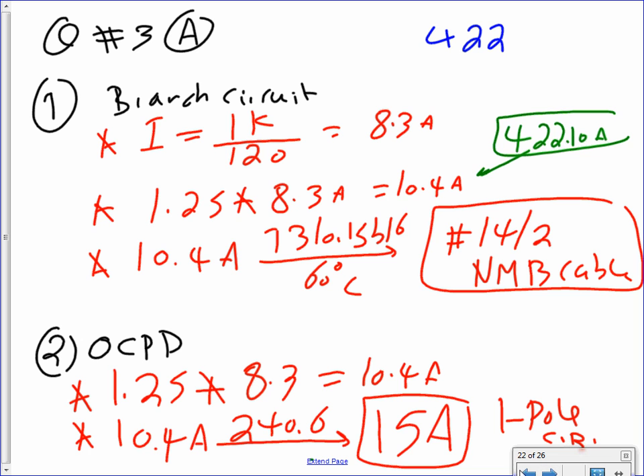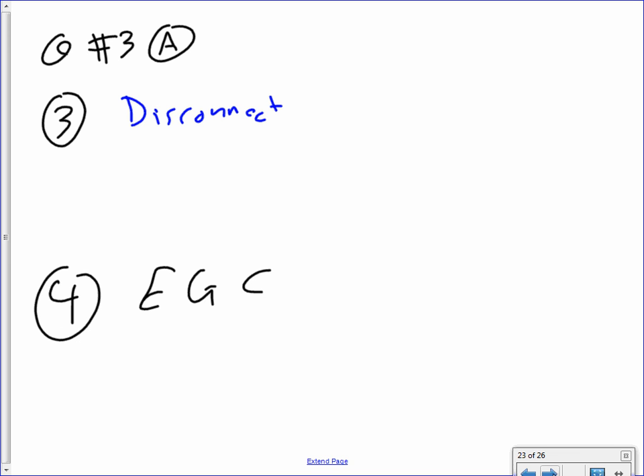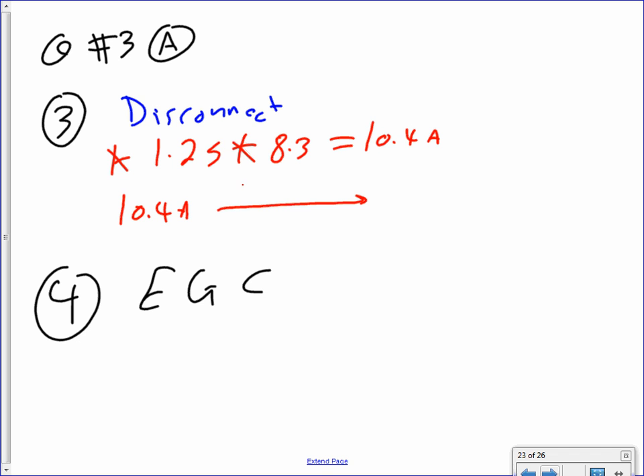Cool. Next, we need to go find the disconnect. What I do personally for the disconnect, my friends, is the same thing. I take the 1.25 continuous load multiplied by my 8.3 amps. The motor gives me 10.4 amps, and then you take the 10.4 amps. This is from 422.30, 422.31, I believe. That will get you guys a 15 amp snap switch.